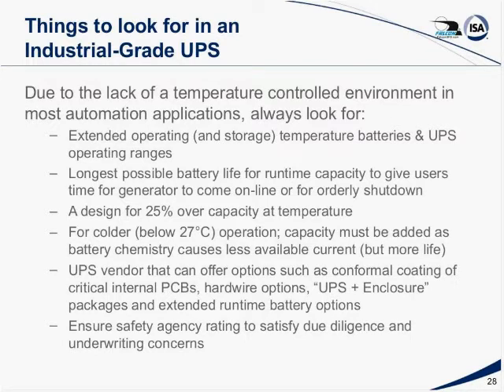with the NEMA 3X or 3R, when you get to 3X, that would imply that you have not only an outdoor environment, but an environment that may have some corrosive chemicals that can cause corrosion in the electronics of anything, UPS or whatever. Conformal coating can only go so far. And in that type of an environment where there's corrosive gases or conductive powders or whatever, a NEMA 4X is a better way to go.